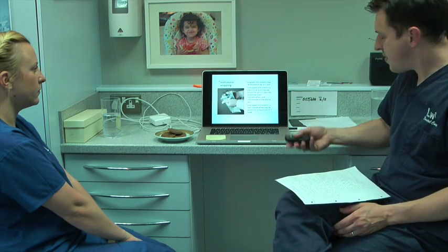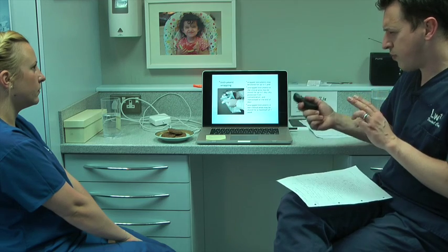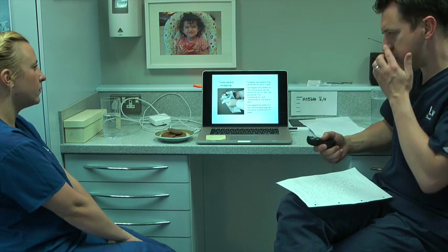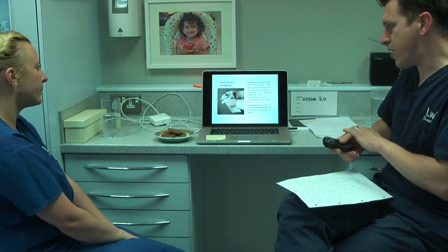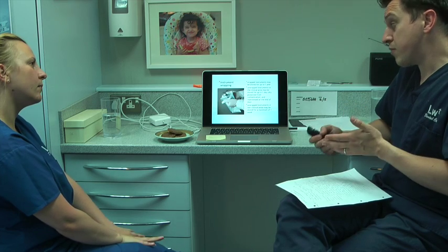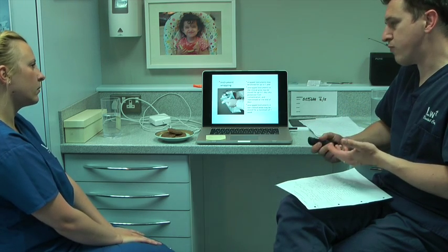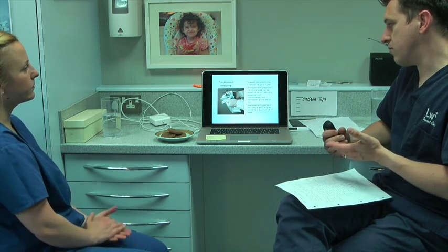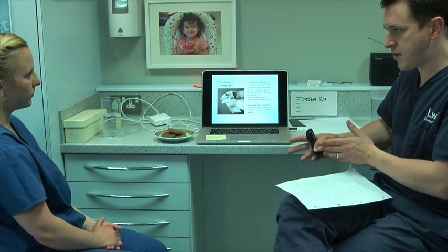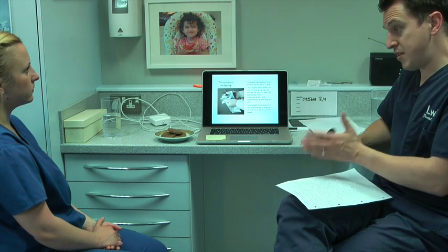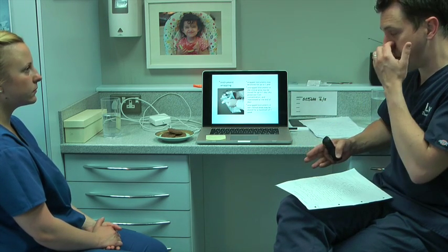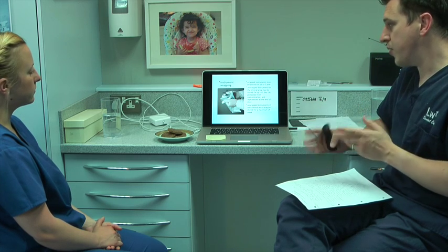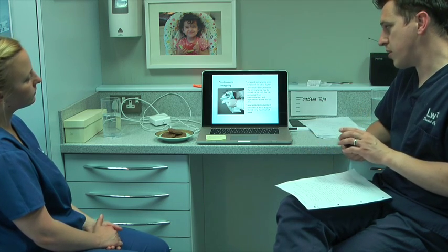Fine. So I said that there was a change from the 2009 edition to the 2013 edition. It mainly comes down to instrument wrapping. So in summary, the wrapped instruments may be stored for up to a year. So as long as it's gone through the sterilisation process and it's wrapped, we need to stamp it to make sure that there's an audit process involved. But those wrapped instruments may be stored for up to a year.